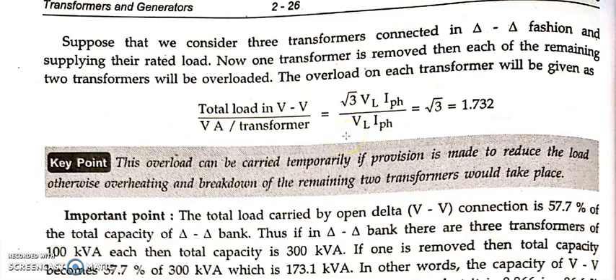So in case, let us assume that a bank of 3 single phase transformers is connected and you have applied full load to that. Okay, yes or not? If you have delta connection, then you can apply full load as per the kVA rating of your transformer, right? Yes. Let us say one of the transformers fails, that is, one of the transformers becomes open circuited. Then what happens? Then there will be an overload on the transformer, yes or not? There will be an overload on each transformer. That overload can be calculated like this.